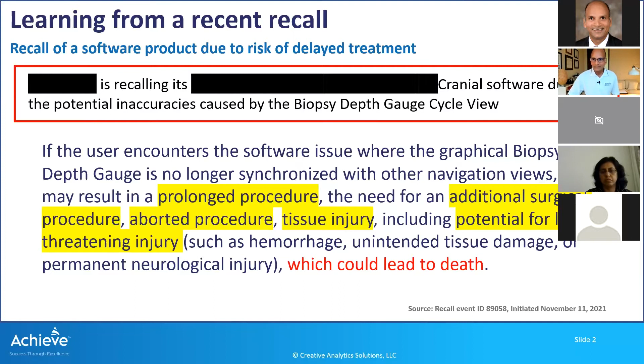Anybody else? Naveen, I have some experience with trying to navigate delay in treatment. Yep. In two experiences I've had, delay in treatment was the harm. So in a risk analysis, there was a sequence of events, there was a hazardous situation, and then delay in treatment was the harm. But if you think about it, in the IMDRF code lists, delay in treatment is actually considered part of Annex F, which is health impact. And so if you're really going to use those codes, you would need to choose a code from Annex E, which is your clinical signs and symptoms.